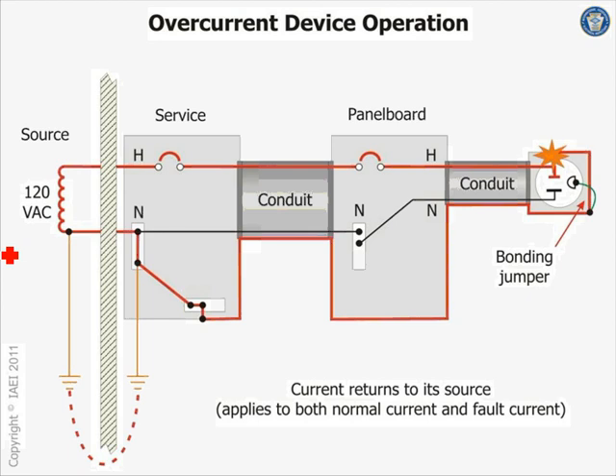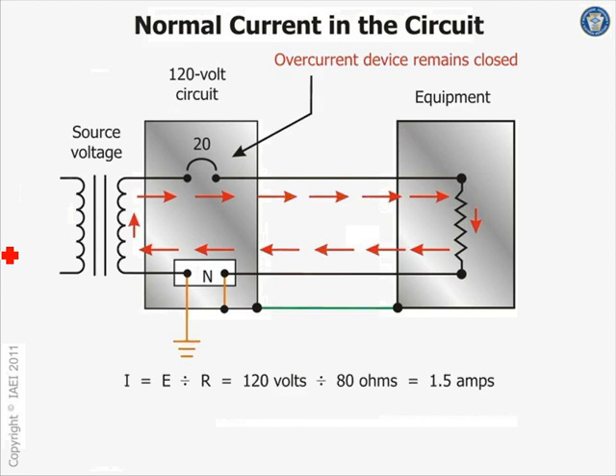If you lose your neutral, in this case, your system will continue to operate. You continue to operate because you're bonded to the ground, so the unbalance will go right through Mother Earth. Obviously, we don't want to depend on it, but that could be your second line of defense if you lose a neutral, instead of burning the building. That bonding here becomes your second line of defense.